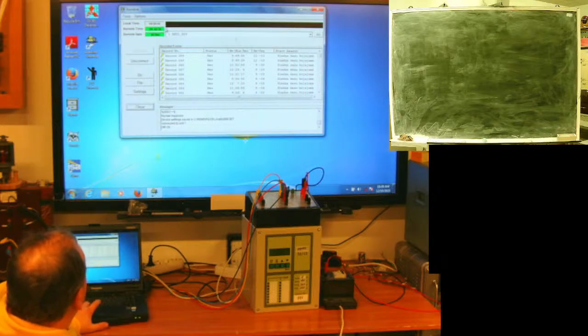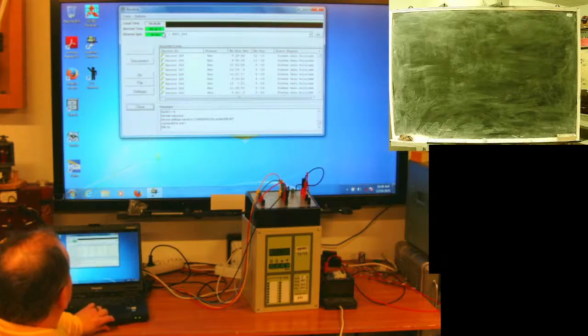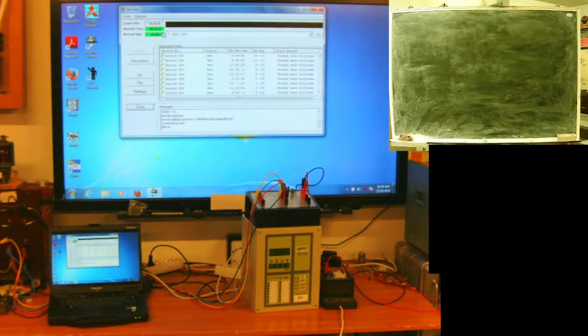Next one, object, time. It's crucial to have a local clock on the device because you need it, even if the device operates standalone, with no bilateral configuration like in differential protection. Anyway, I need time to understand what happens when. In case of system emergency, system fault, what will I do? I need to build a big picture of events. To build a picture, I need a uniform time. Without it, it's bullshit.